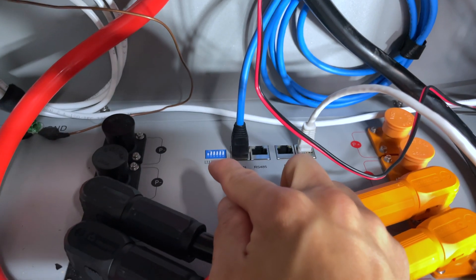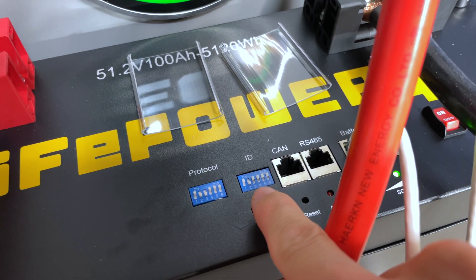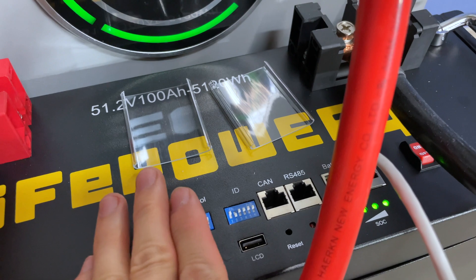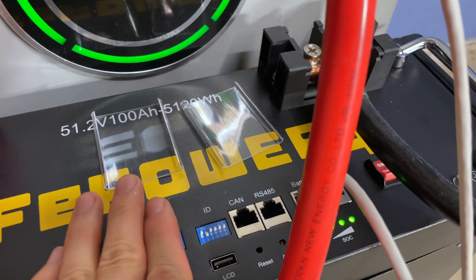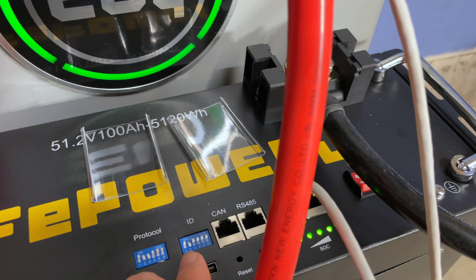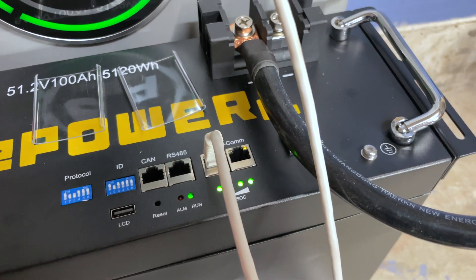The super critical thing here is that your host battery always needs to be address one. You can see DIP switch one is down, two through six are up on the host. My second battery has DIP switch two down, making it address number two. The protocol setting applies to CAN bus and RS485 communication, but the ID address is what's really critical. Connected via standard RJ45 CAT5 cable.